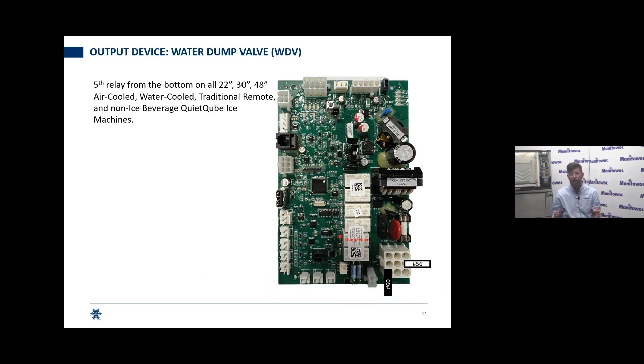Again, the thing that I'm wanting to stress today in our spotlight is if the LED is lit, you have to verify power, either at the components or at the board. You can go across the two wires, find your common 56 and find L1, go into that component and check. Dump valve says it's on because you've got the relay, you've got no power, relay's not sending out. Dump valve is not letting water through, you do have power, you've got a clogged up drain line or a restricted dump valve or a defective dump valve.